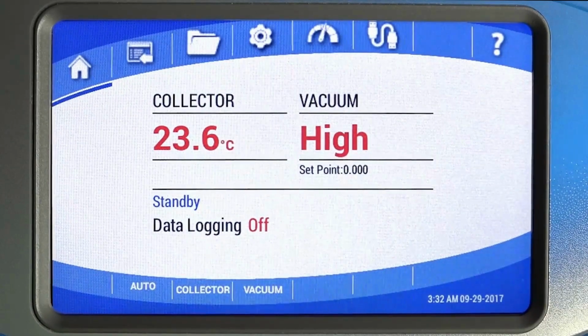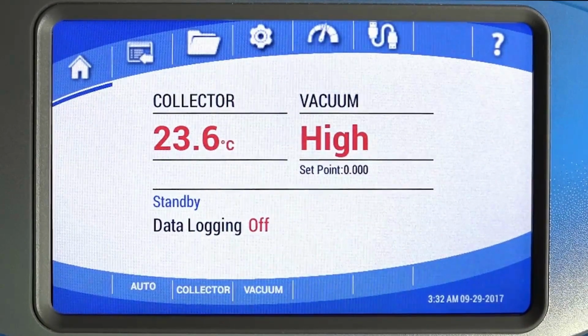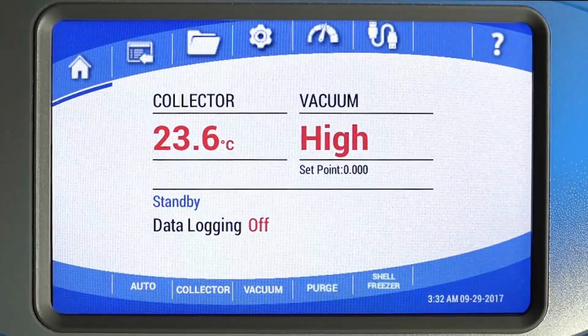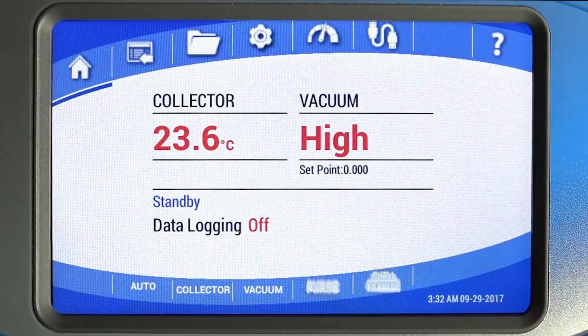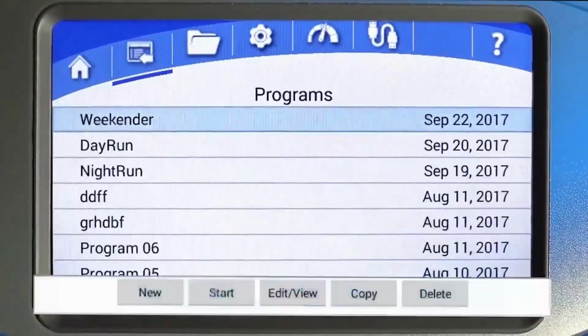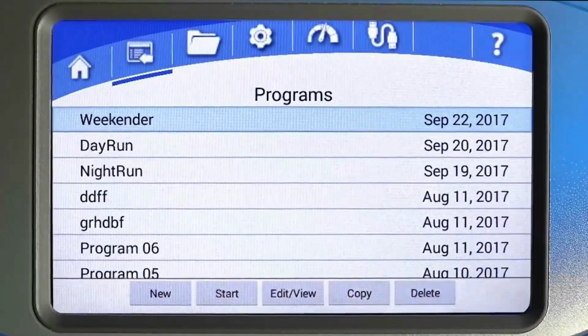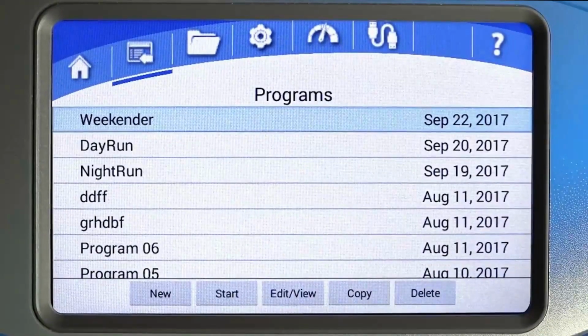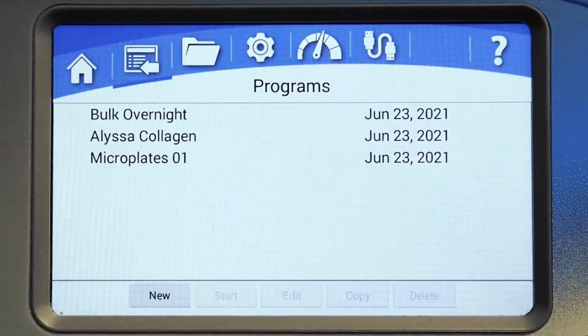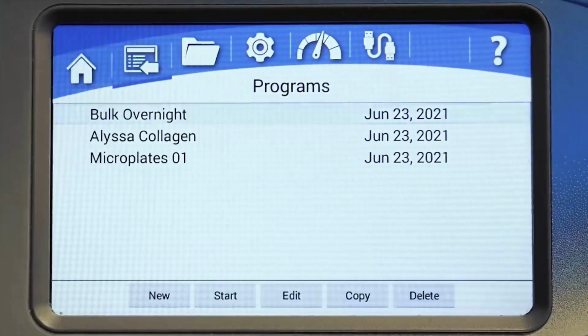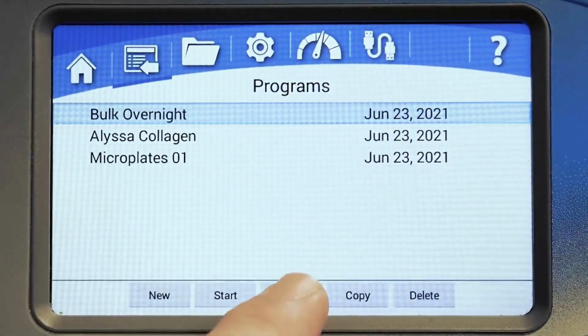The vacuum level can be set by pressing the vacuum button. Freeze dryers that include the optional purge valve, shelf freezer, or mini chamber will display the buttons to control them here. Under the Programs menu, you can create a new program, start a program, or view and edit programs. You can also copy or delete programs from this screen. When you create a new program or edit an existing one, you can edit the program's name.